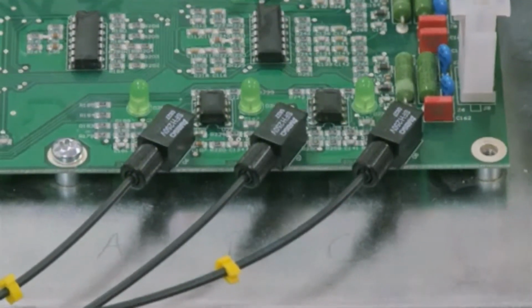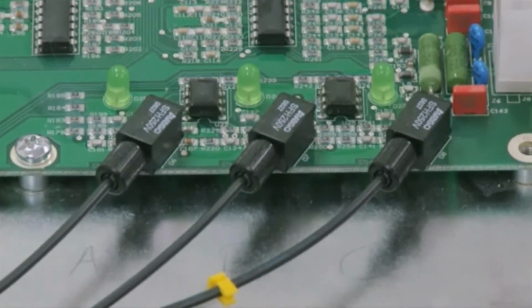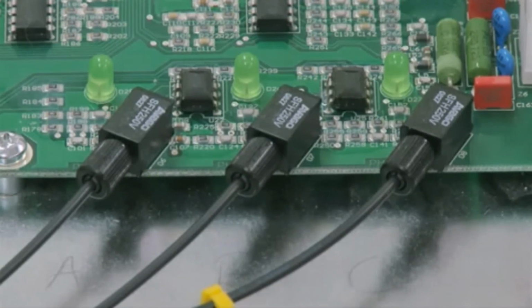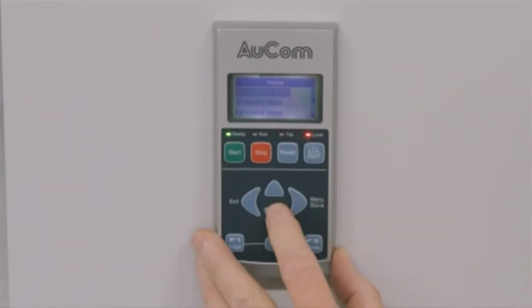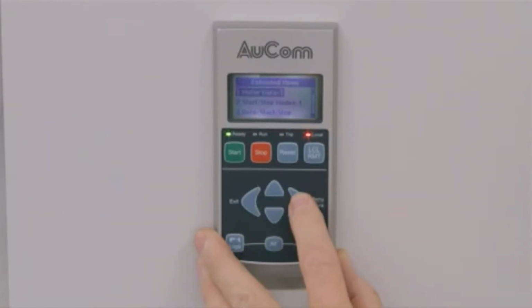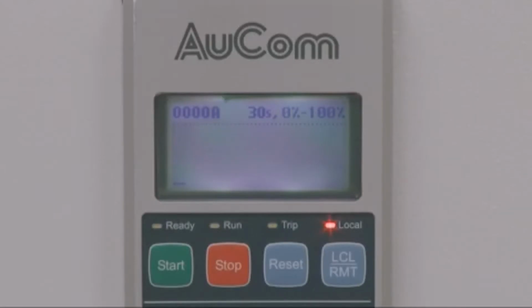For complete electrical isolation, communication between the low voltage controller and the high voltage power assembly is via fibre optic cables. Your MVX features simple, plain language, so you don't need to look up trip code tables, with extensive metering information to allow easy monitoring of motor performance at all times.